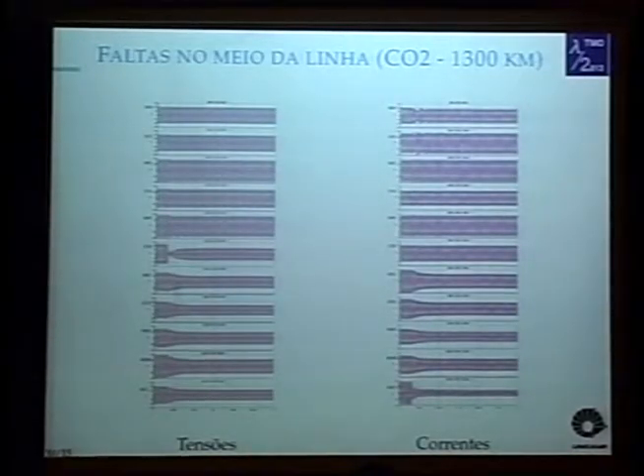But why are faults in the middle of the line complicated? To show this, we have all the voltages and the currents for a fault happening in Colinas 2, 1,300 kilometers from the sending substation, exactly in the middle of the line. So here we have a fault happening in Colinas 2. The voltages in the Serra da Mesa 1, Gurupi 1, Miracema 1, Colinas 2 substations, up until Imperatriz, basically do not change. No disturbances happened.